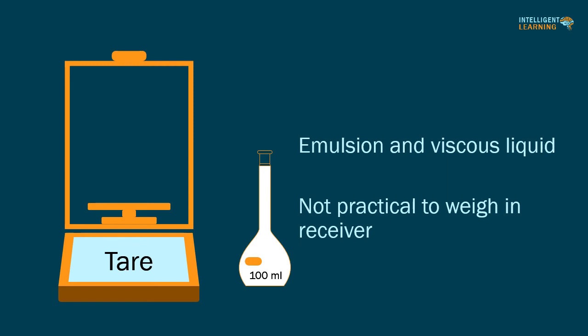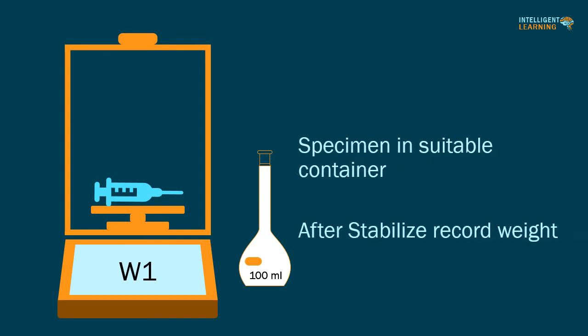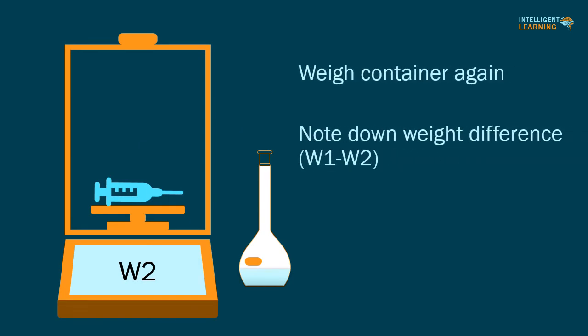Dispensing weighing is typically used for weighing emulsions or viscous liquids such as ointments. In these situations it is not practical to weigh the material into a typical receiver. The analyst should tare the balance, then place the sample on the balance in a suitable container — for example, a bottle, tube, transfer pipette, or syringe — that has been wiped clean on the outside. Record the weight after the balance display stabilizes. Transfer the desired amount of sample to an appropriate receiving vessel, such as a volumetric flask. Place the pipette or syringe back onto the balance. The difference in the two weighings is equal to the weight of the transferred specimen.